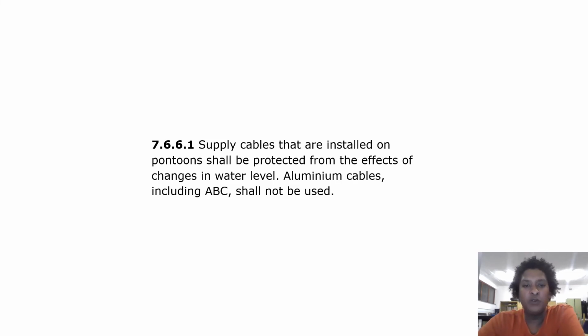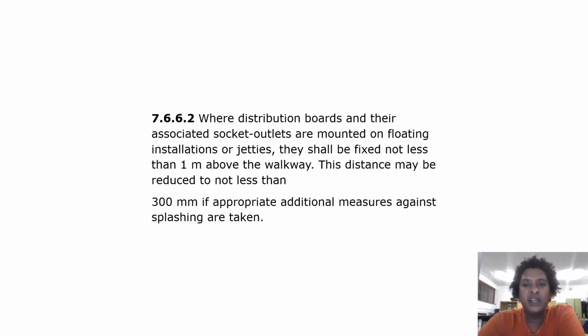Supply cables that are installed on pontoons shall be protected from the effects of changes in water level. Aluminium cables, including aerial bundled cables, shall not be used. Where distribution boards and the associated socket outlets are mounted on floating installations or jetties, they shall be fixed not less than 1 meter above the walkway. This distance may be reduced to not less than 300 millimeters if appropriate additional measures against splashing are taken.